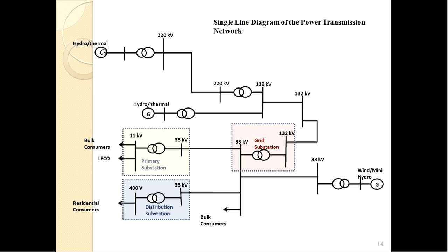From a grid substation, it is brought down to 33 kV, and then to a primary substation - we may have different names. So this is 33 kV, medium voltage or low medium voltage distribution. Then from 33 kV, it may go to 11 kV, or like in this distribution substation, 33 kV to 400. These are the transformers that you'd see on your electricity poles, pole mounted transformers, basically used for 33 kV to 400.